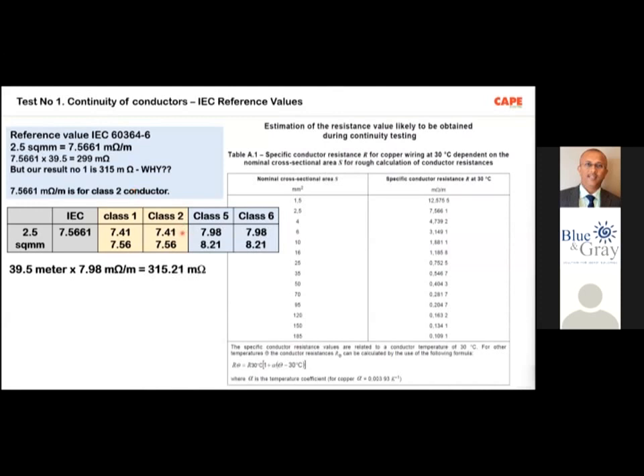Class 2 and class 5 are actually for PVC insulated conductors, let it be FR, FRLS, or all these things. PVC insulated wires are available with 2 types of conductors, class 2 and class 5. Now look at the resistance of both wires: 7.41 and 7.98, 7.56 and 8.21. The second one is the resistance of the tin plated copper, and the first one is the bare conductor. If we calculate 7.98 into 39.5 meters, then we accurately get the value which we got, 315.21 milliohm. So we failed the test because we used a class 5 conductor, which we are not supposed to use for the fixed part of the electrical installation. For the fixed part of the electrical installation, we are supposed to use copper wires with class 2 copper.